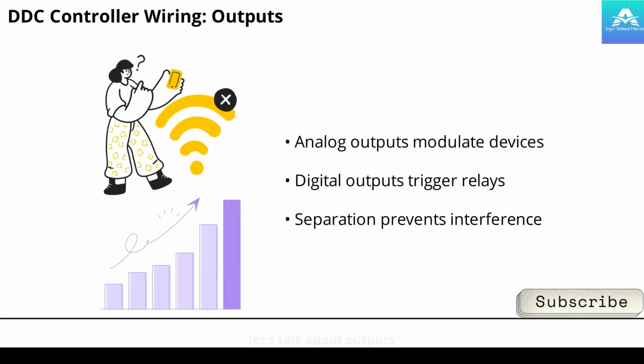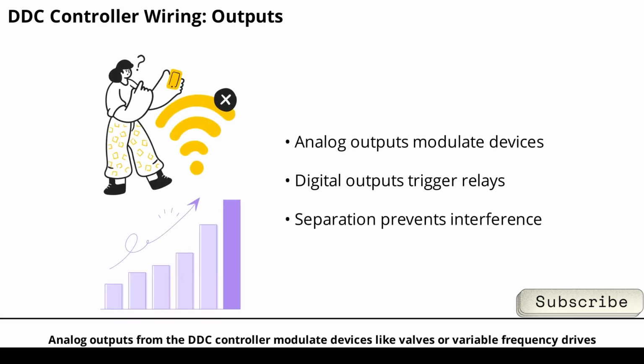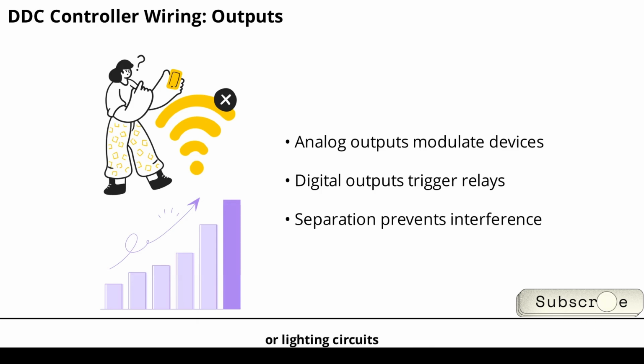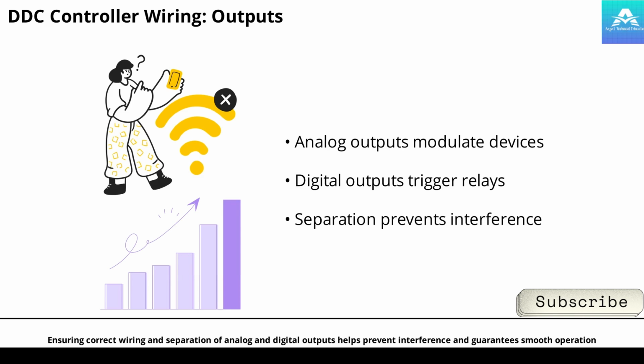Now, let's talk about outputs. Analog outputs from the DDC controller modulate devices like valves or variable frequency drives, adjusting things like water flow or fan speed. Digital outputs typically trigger relays to start or stop equipment. Think fans, pumps, or lighting circuits. Ensuring correct wiring and separation of analog and digital outputs helps prevent interference and guarantees smooth operation. Together, these input and output connections form the nervous system of your building's automation.